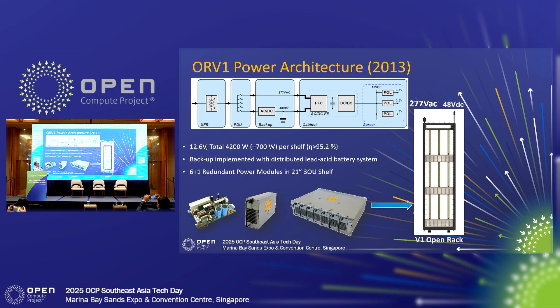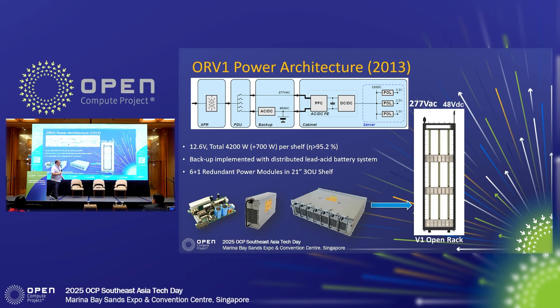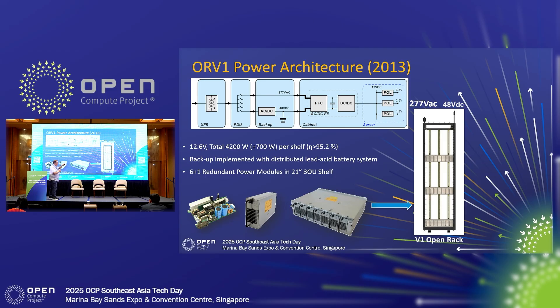Way back in the beginning, around 2011–2012, the folks at Meta decided to develop rack power. They created an OCP rack, which is 21 inches wide versus the typical 19-inch rack. They put three bus bars down the back to deliver power and three shelves so power was accessible to the servers. You could put the power supplies in, then put the servers in wherever you wanted them and get power from the rack. The concept was good — it made sense — and they were off and running by 2013.